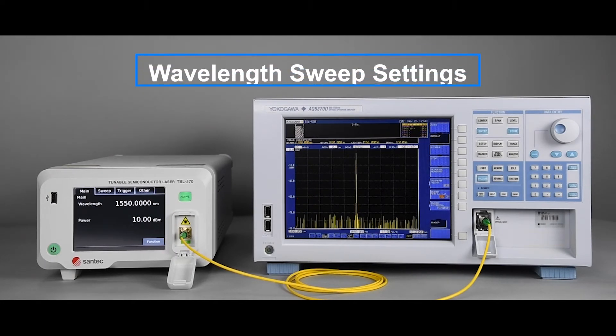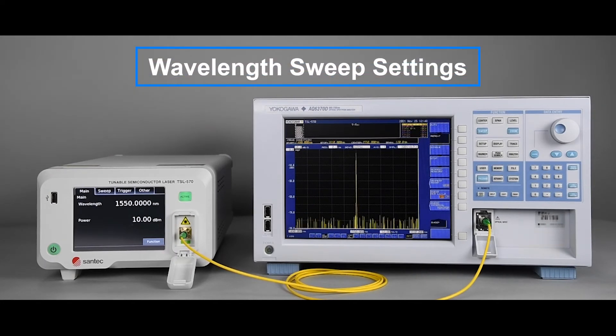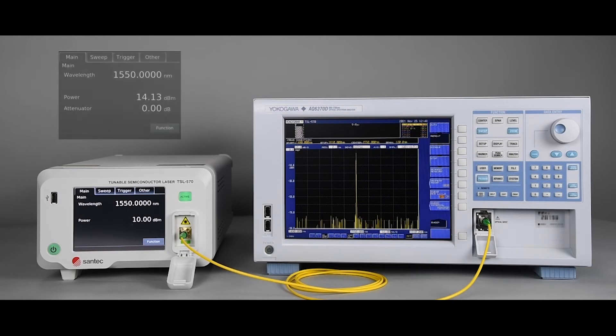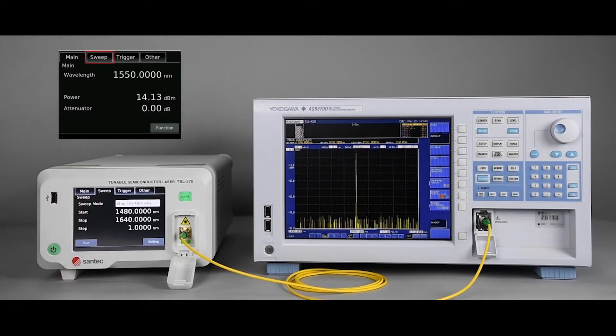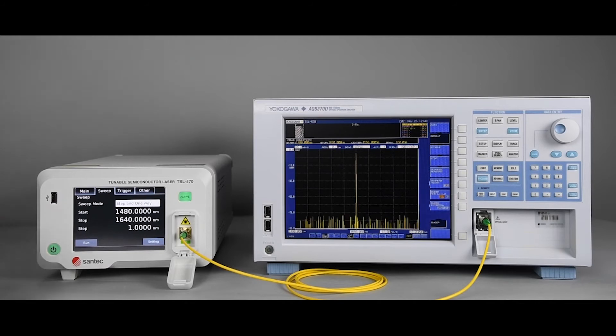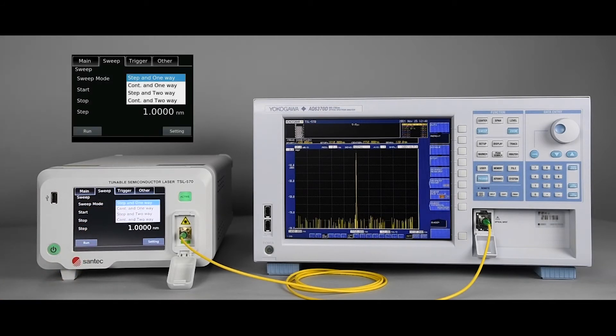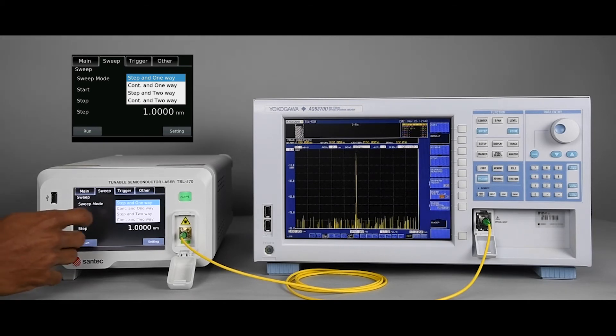Now, let's set the TSL 570 to perform a wavelength sweep. For this, we go to the Sweep tab. First, we have to select a sweep mode from the four available sweep modes: one-way step mode, one-way continuous mode, two-way step mode, and two-way continuous mode. In this tutorial, we'll set the TSL for one-way continuous mode.